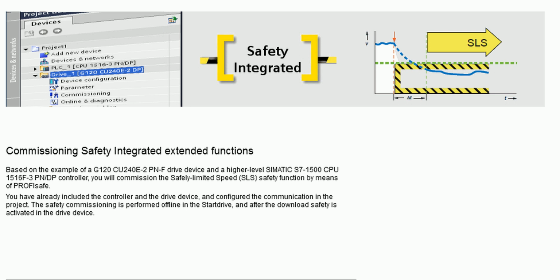Based on the example of a G120 CU240E-2 drive device and a higher-level SIMATIC S7-1500 CPU controller, you will commission the Safely Limited Speed (SLS) safety function by means of PROFIsafe. You have already included the controller and the drive device, and configured the communication in the project. The safety commissioning is performed offline in the Startdrive, and after the download safety is activated in the drive device.